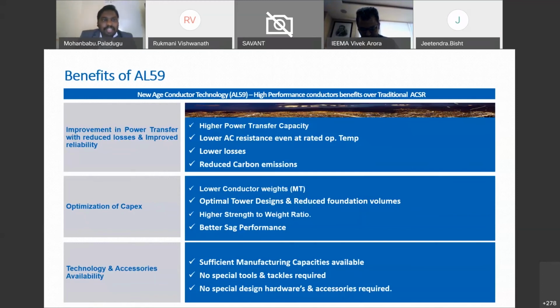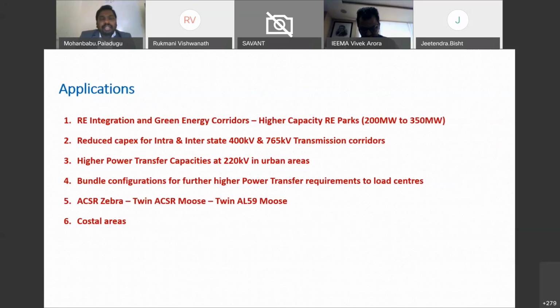Now coming to the applications part. Now the major generation sources coming to India are mostly on the RE. So for RE integrations, at the central level and the state levels, we are planning a large number of corridors to integrate this RE generation. So today RE parks are coming up with high capacities, more than 200 to 350 megawatt, where traditional 220 kV lines may not carry this much capacity with the thermal rating limitations. So in those applications, this AL59 with this 20 to 25% higher capacities will be the best alternative at a 220 kV level to the ACSR conductors.